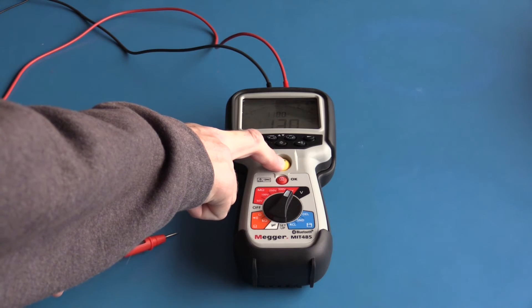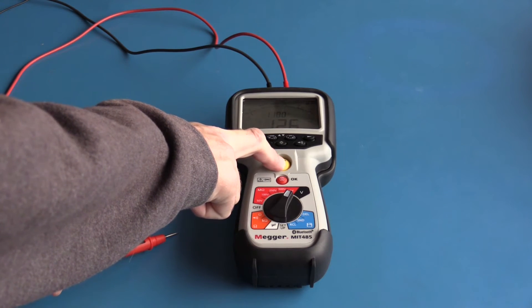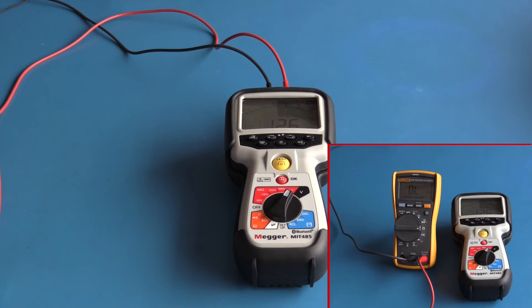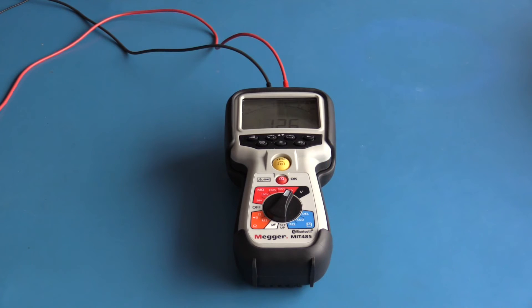This reading is only telling me that there is a path to ground. This test just demonstrates the need sometimes for a higher voltage when making resistance measurements. Tests like this would be performed on motor windings where you're looking for a breakdown in the insulation.